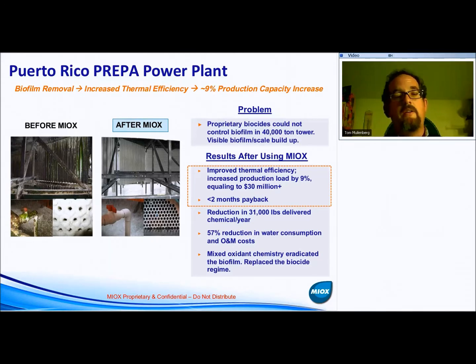Looking at the photographs — which are very easy to read, before and after, they really speak volumes. On the left-hand side, the baffles and mist screens on the cooling tower are coated with algae and biofilm. On the right-hand side, they look practically brand new. All the structurals are clean, the baffles are clean — just after making the switch over to the mixed oxidant.